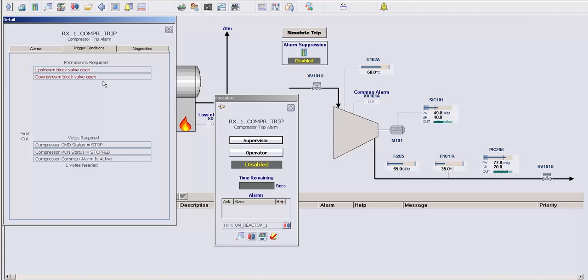So in this example, I'm saying that unless both upstream and downstream valves are open, I don't want this alarm suppression module to be armed and running.